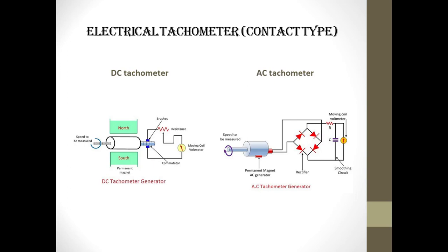Disadvantages of DC tachometers are: number one, brushes on small tachometer generators often produce maintenance problems as their contact resistance may vary and produce appreciable errors. Thus, the commutators and the brushes require periodic maintenance. Number two, the input resistance of the meter should be very high as compared with the output resistance of the generator. This is required to limit the armature current to small values. If the armature current is large, the field of the permanent magnet is distorted, giving rise to nonlinearity.